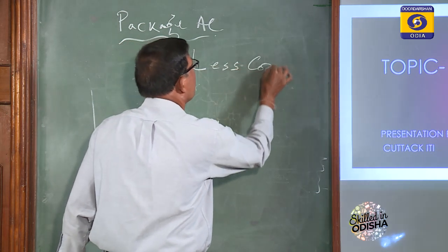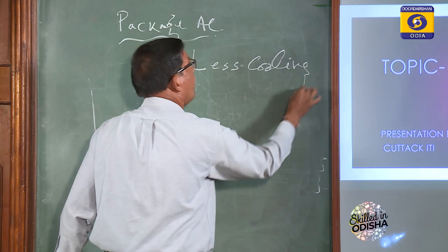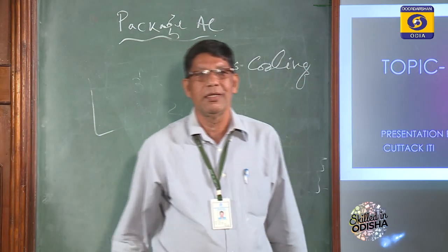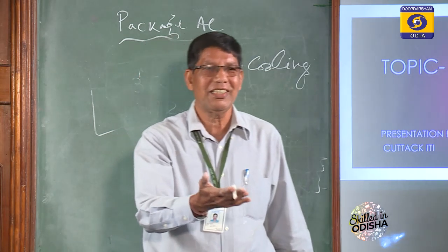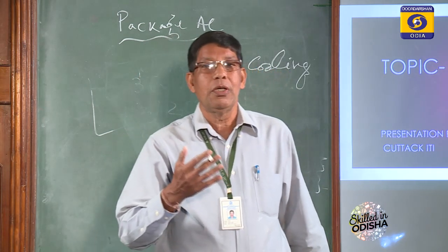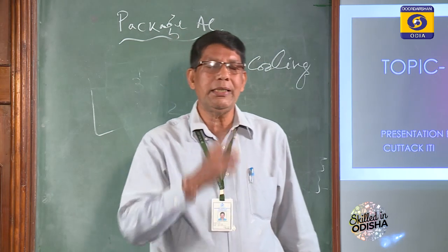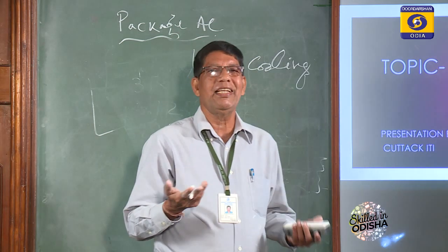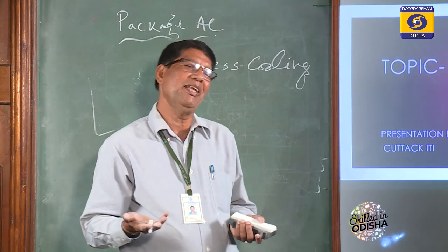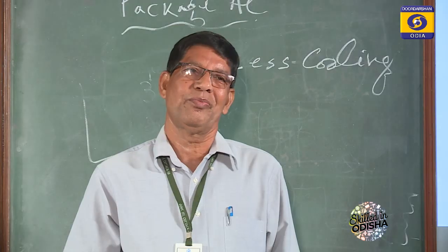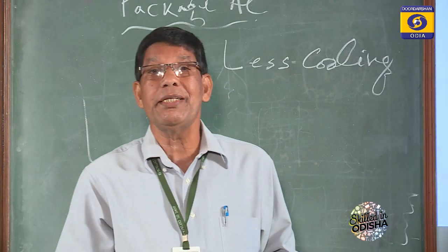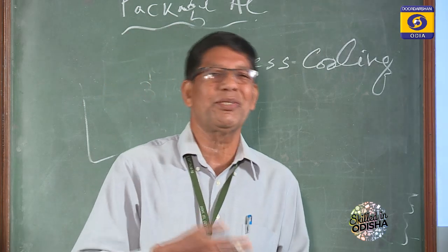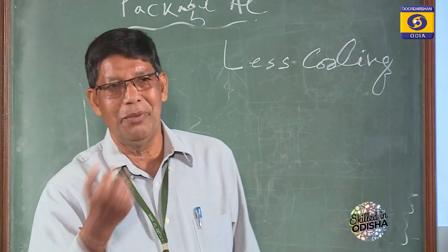Less cooling. What are the causes? Can you tell me? Yes? Suppose there is less refrigerant. It is the main thing. If there is less refrigerant, the cooling will be less. Then low voltage. If the voltage is less, the speed of the compressor will be less, so cooling will be less.